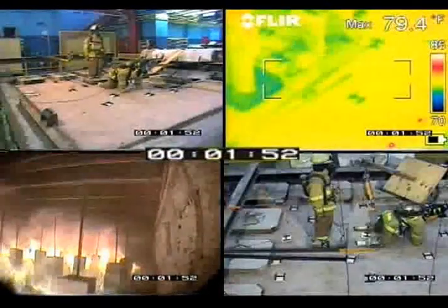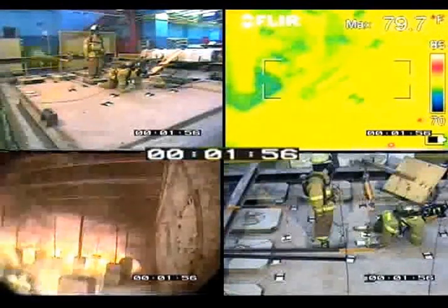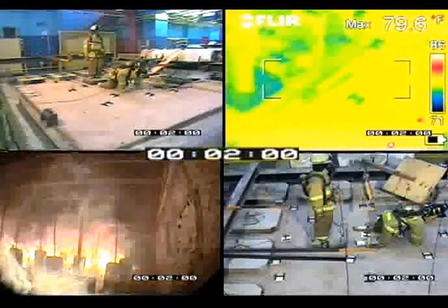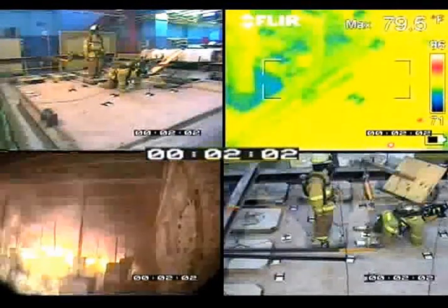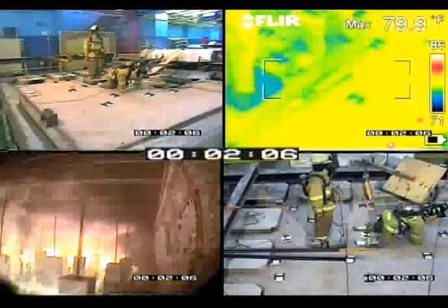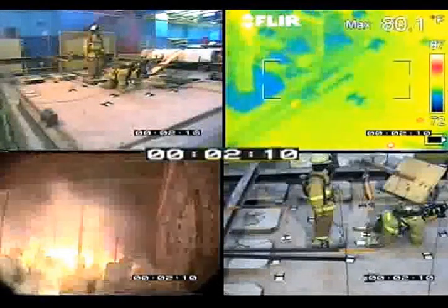2 minutes into the test, smoke is visible, emitting from breaches in the fire stopping seal between the perimeter test frame and the floor. 3 small breaches are visible at the bottom of the TIC view. UL staff note the floor assembly beginning to vibrate, but the vibrations are not yet observable in the camera view.